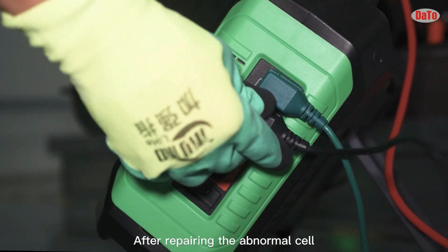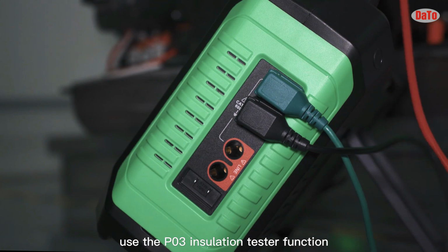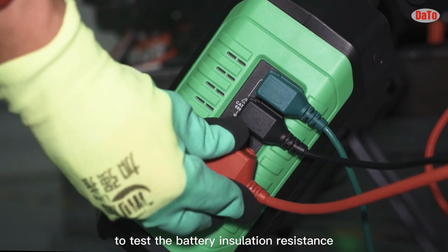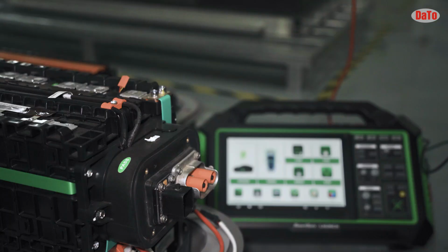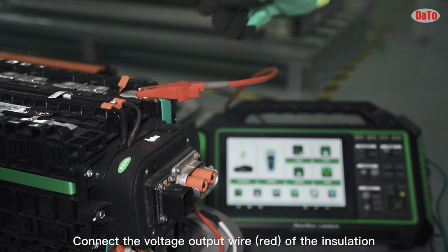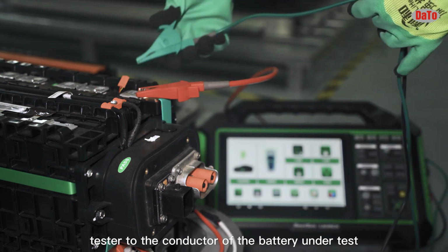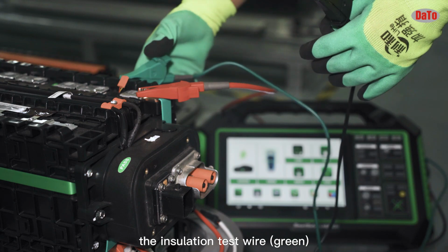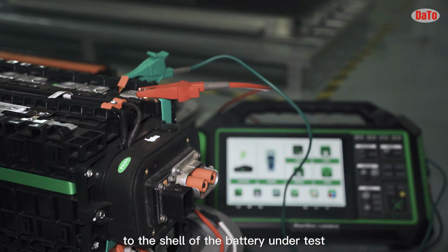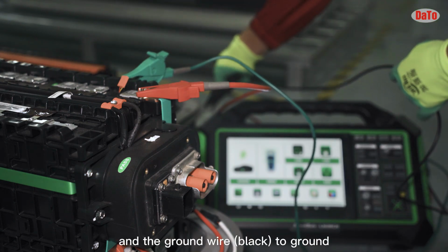After repairing the abnormal cell, use the P03 insulation tester function to test the battery insulation resistance. Connect the voltage output wire of the insulation tester to the conductor of the battery under test, the insulation test wire to the shell of the battery under test, and the ground wire to ground.